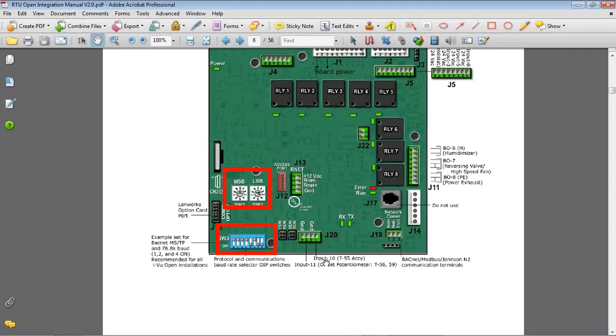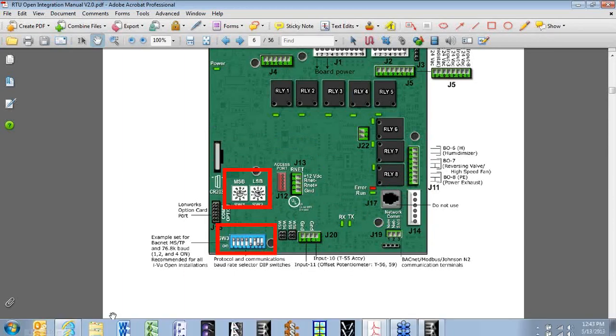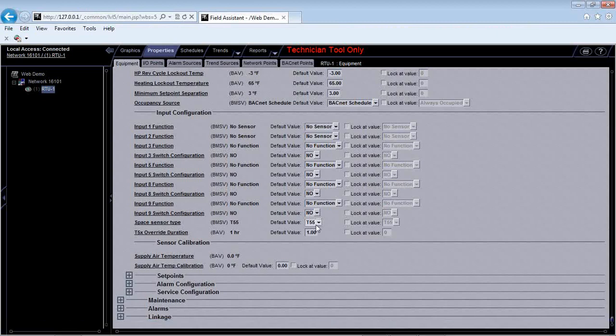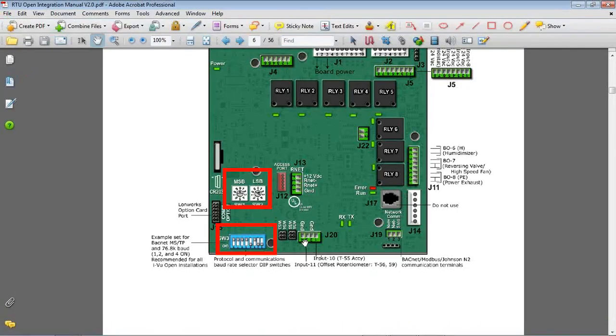It would wire into input 10 on this plug. It actually says a T55. Okay, a T56 is a 10K Type 2 thermistor, but it also has a slide bar for a 100K potentiometer. So you can do set point adjustment with that, okay? So, again, this is all depending on what type of sensor you have in the space, I can select T56, and then I would look at my install manual for where I would need to wire in my T56 sensor, okay?